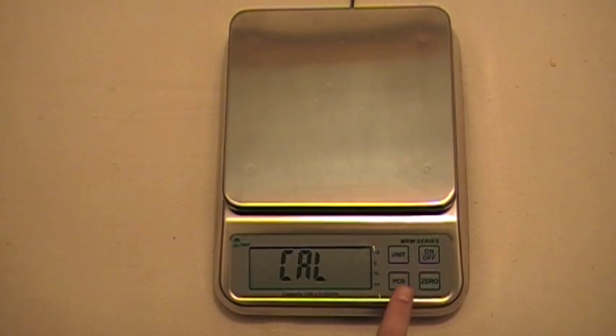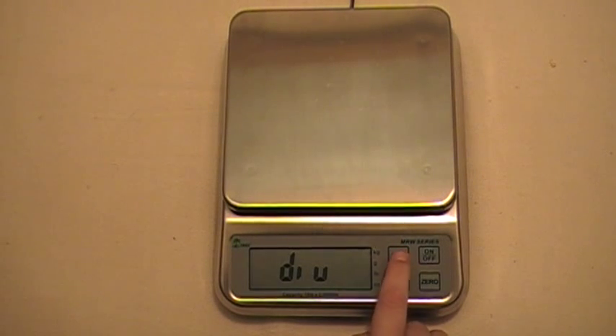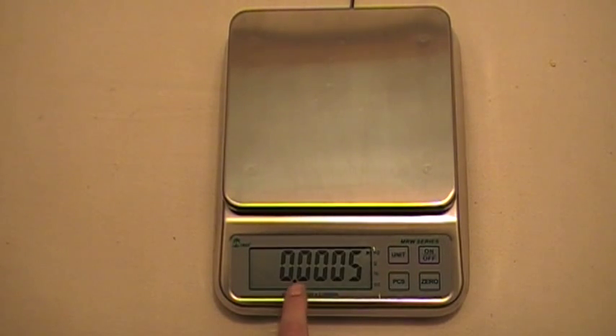Now we're going to press the pieces key again to move to the next menu — the division menu. To find your division, look at the bottom of your scale. On my scale it says 0.0005 — that's the division. Your scale might be different. To change it, press the unit key. There are several different selections, but we're using 0.0005 and we're going to confirm that by pressing the pieces key.